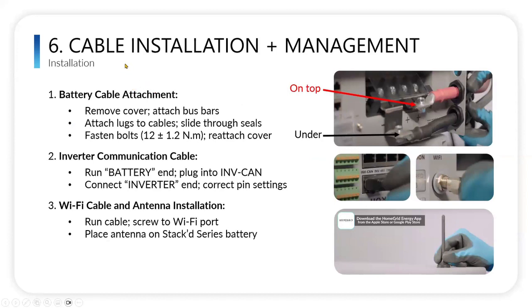So the cable installation and management, like I was mentioning before, on our 48 volt BMSs, you will have these bus bars, and you're going to connect the cabling to those bus bars. The positive cabling will go on the top of the bus bar, and the negative cable will go on the bottom.